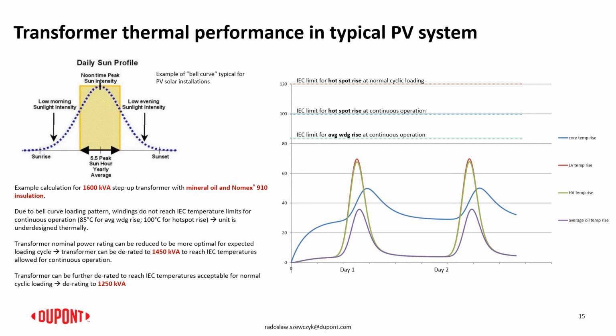So there is a possibility of optimizing the transformer design to make sure that the power rating could be even derated, it could be even reduced compared to the power rating output of the inverter, and with this the cost of the transformer could be reduced.